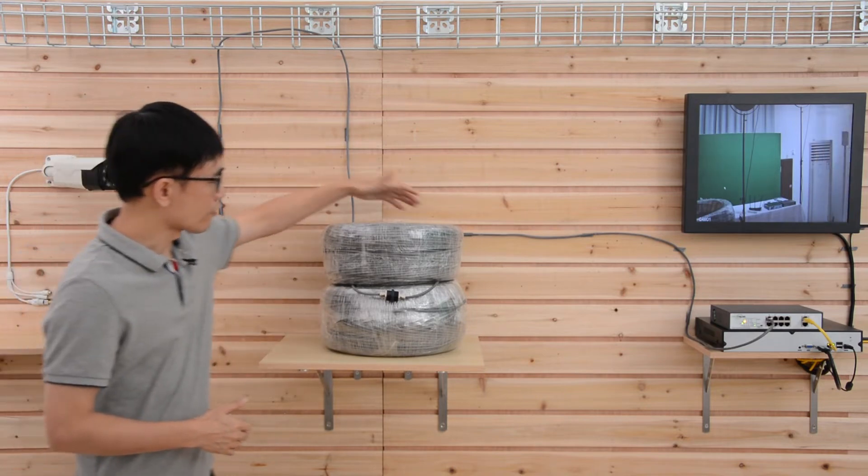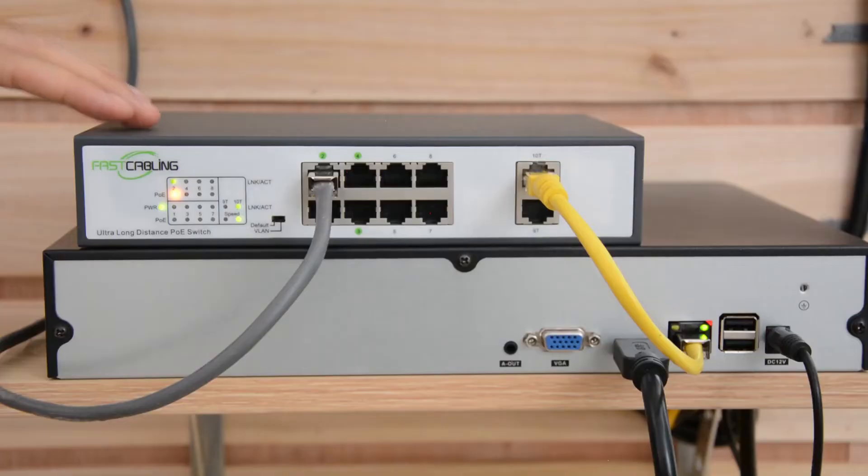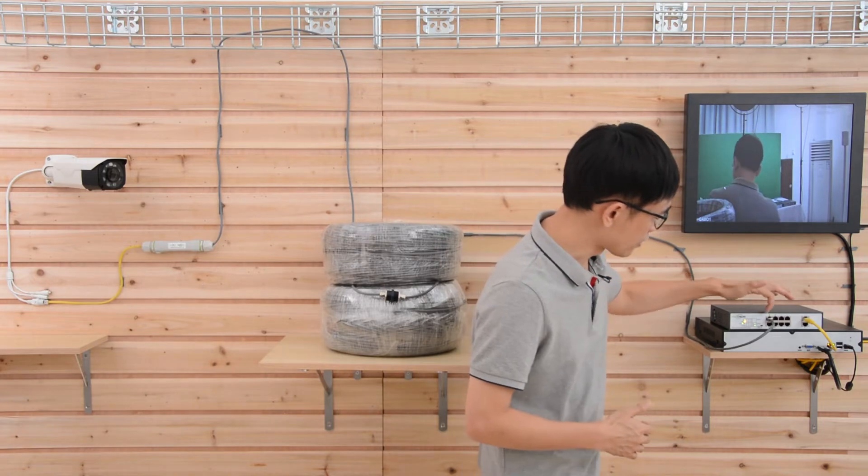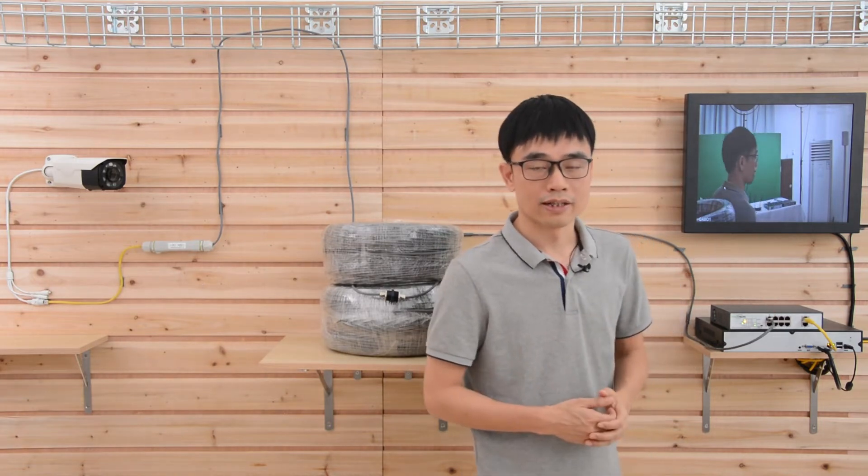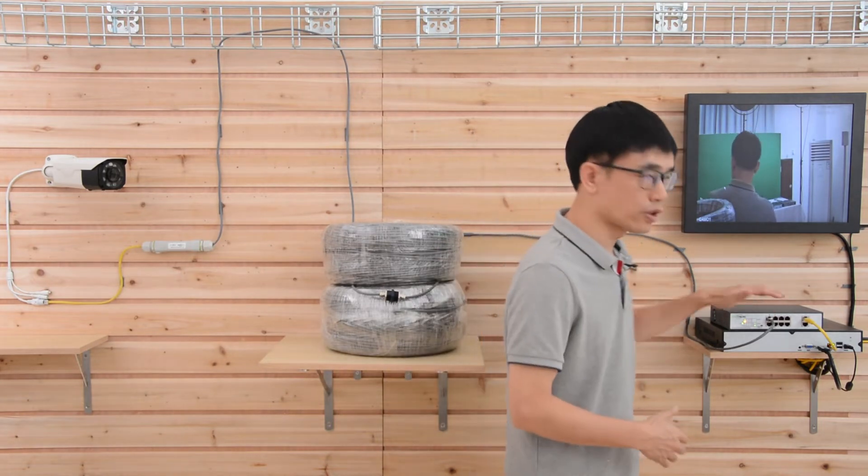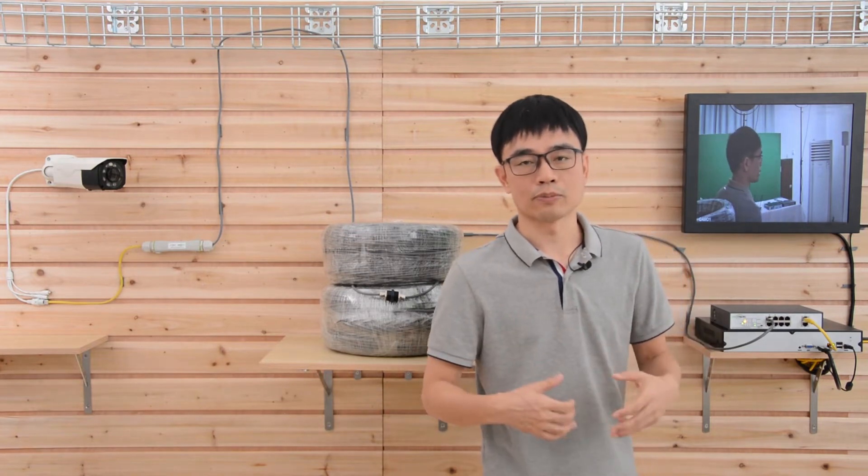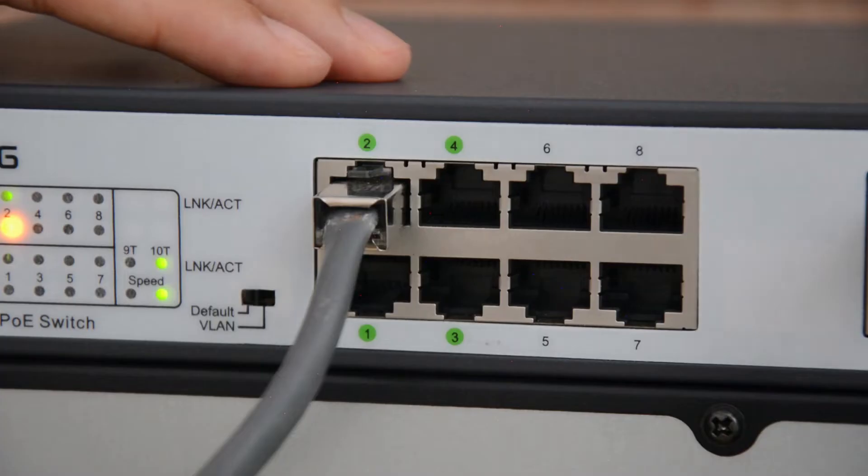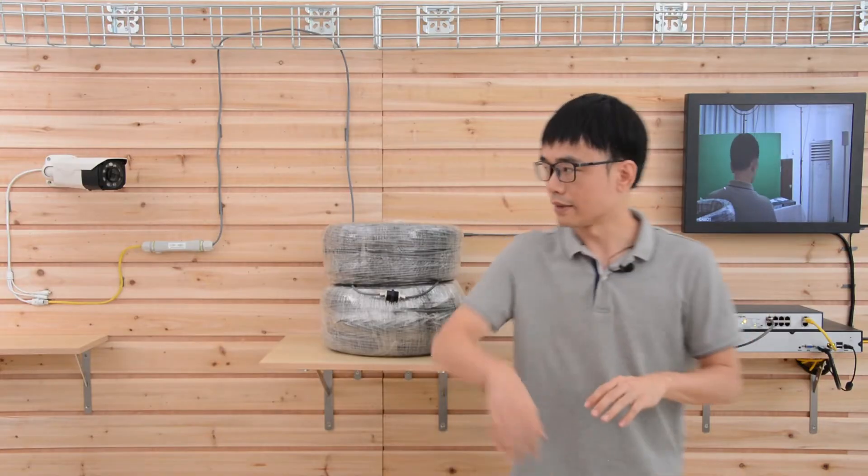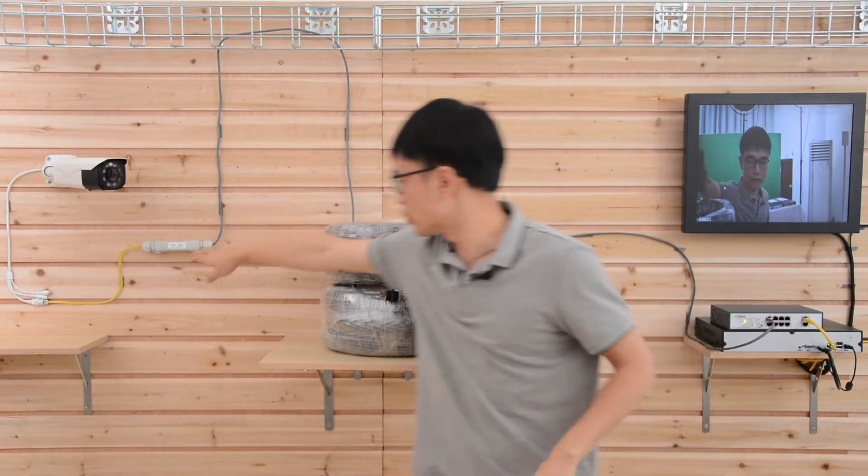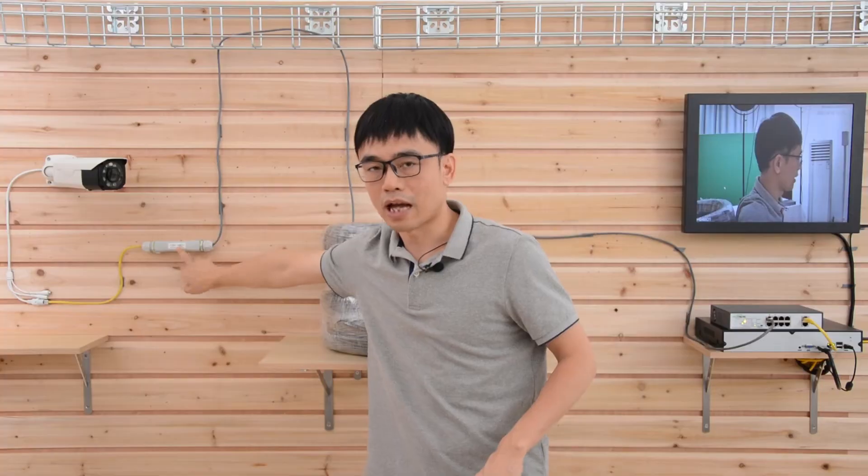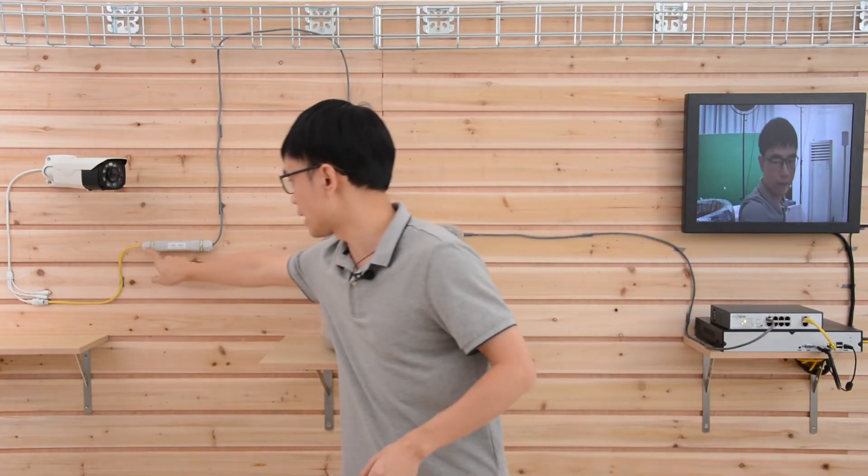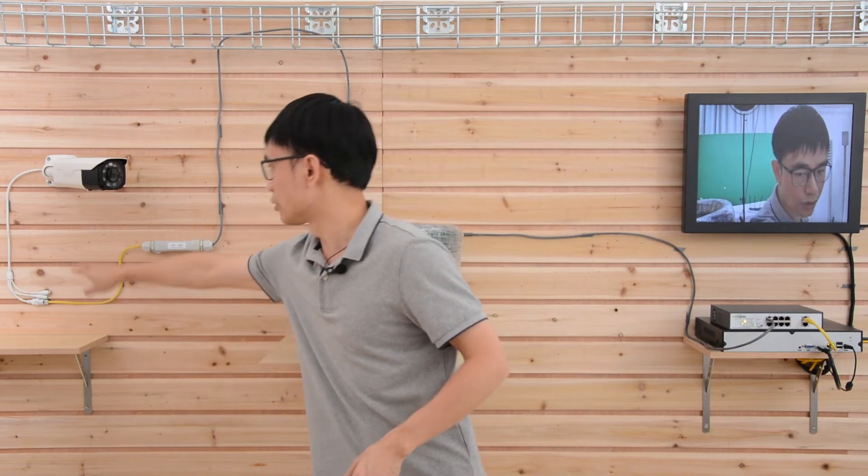And now one end of the cable is connecting to this long run PoE switch. It looks like a regular switch. Only the first four ports support long run. The maximum distance between this switch to the edge device can reach up to 2500 feet. And now I'm using port number two and connecting to the cable. And at the other end, you can see we do need one PoE extender sitting here. I will explain why we need this PoE extender. And after the PoE extender, we will use a short patch cord to connect to the camera.